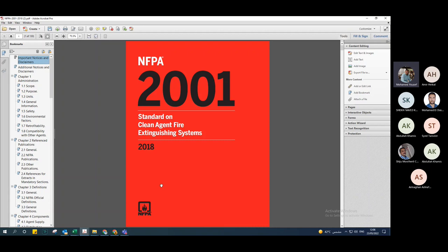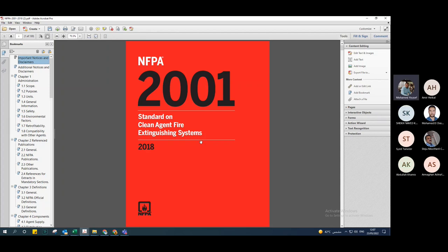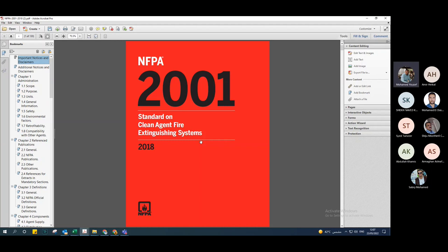The clean agent systems we are speaking about are the two famous ones: the Novec system (Novec 1230) and FM200. To calculate the gas for any room, we need to know the volume of the room. The principle of working of Novec or FM200 system is based on the concentration of gas inside the room itself. We need to know the net volume of the room, and the second issue is the concentration of the gas inside the room.